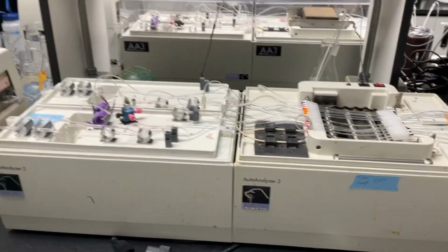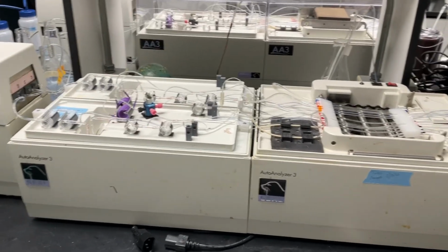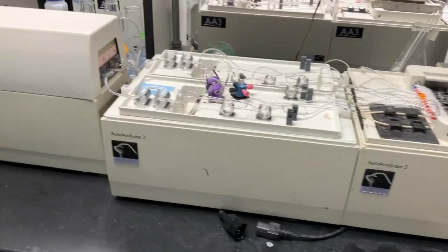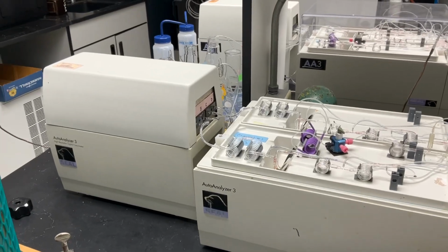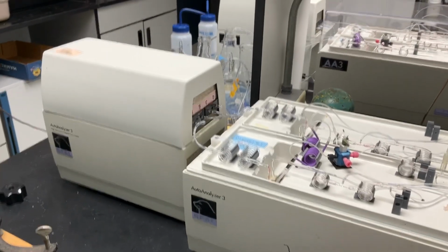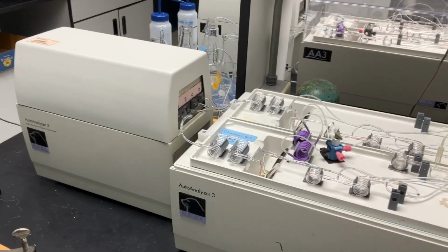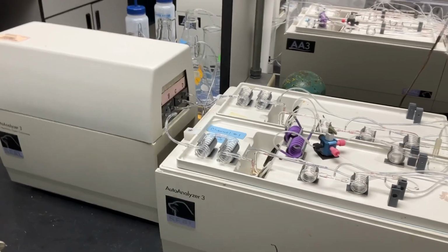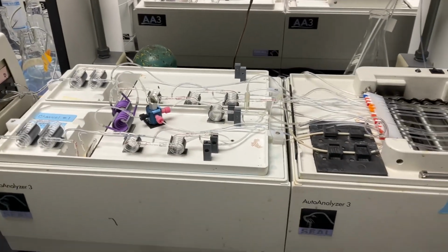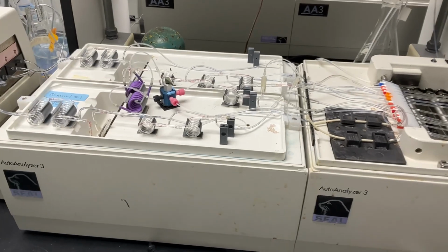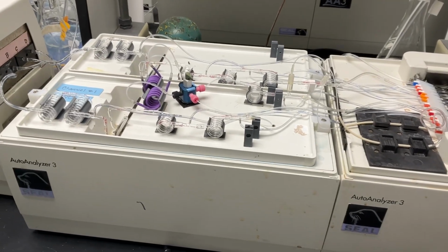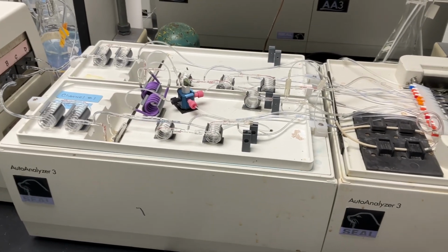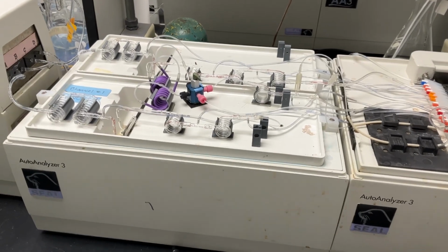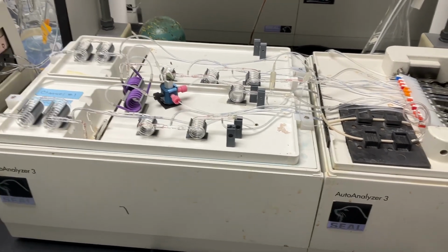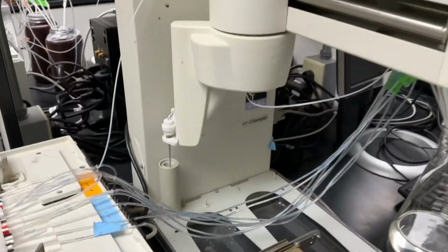So this is the machine a little more opened up. This is what it looks like when it's not running, unlike the video I just showed you. As you can see, all of the glass tubes are clear, and those glass tubes are actually what different reagents and your samples flow through to end up all the way at the left side where there's a sensor that can actually detect any color changes that have happened to your system. And those color changes are what are associated with your nutrient quantities. So we'll be able to talk more about that later when I show you some of those color changes and the way that the software interprets it.